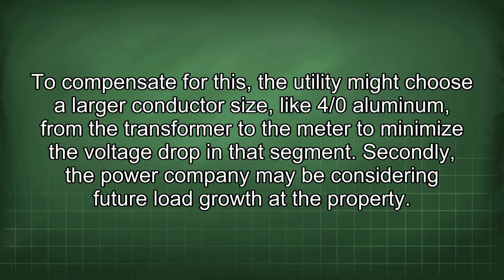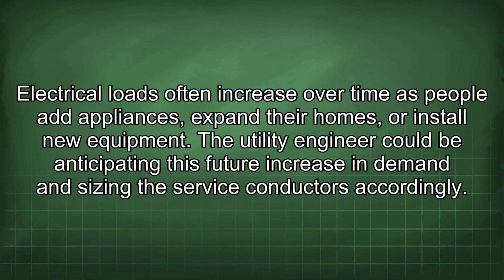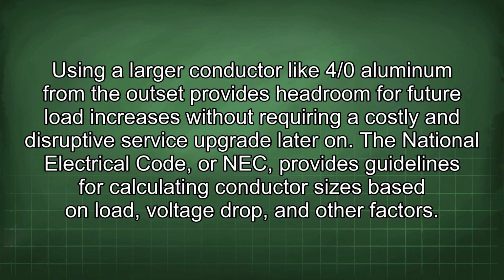Secondly, the power company may be considering future load growth at the property. Electrical loads often increase over time as people add appliances, expand their homes, or install new equipment. The utility engineer could be anticipating this future increase in demand and sizing the service conductors accordingly. Using a larger conductor like 4/0 aluminum from the outset provides headroom for future load increases without requiring a costly and disruptive service upgrade later on.